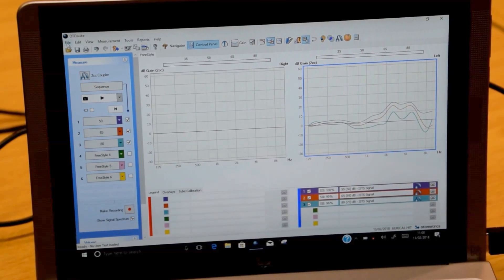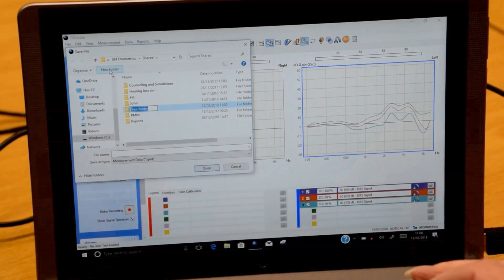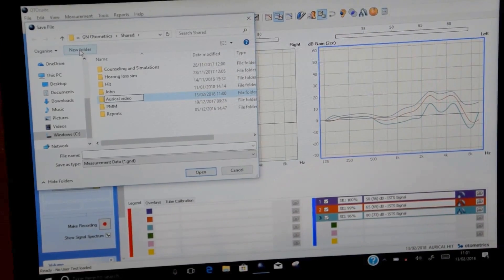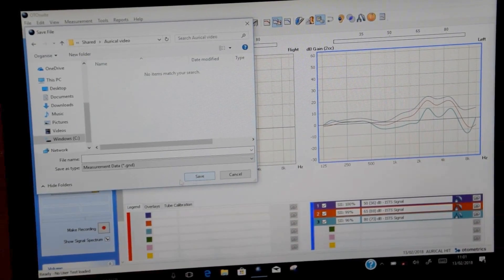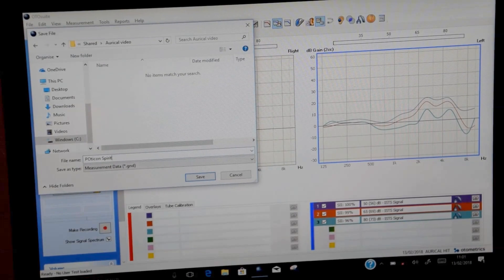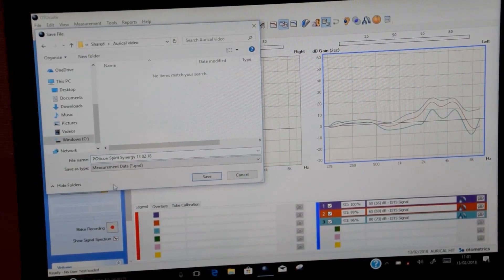We're now going to store that curve by going to File, Save As. I'm going to create a new folder which I'm going to call Aurical video — this could be the child's name, could be the child's identifier, whatever you feel is appropriate. So we now open that folder and put a sensible file name: Oticon, and the date. So we save that file.